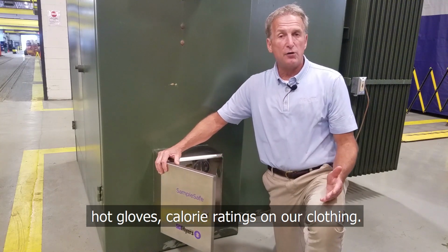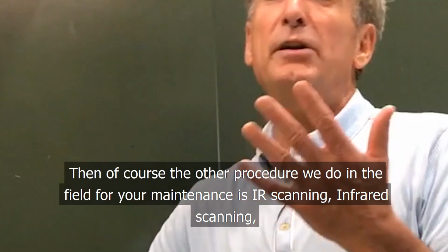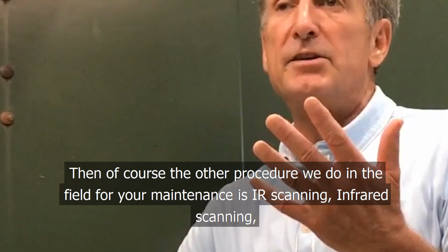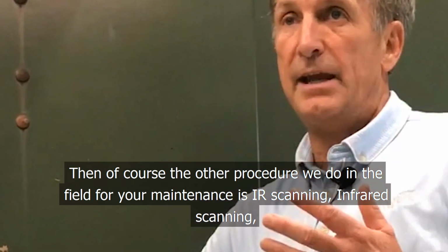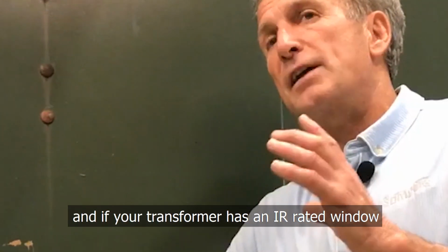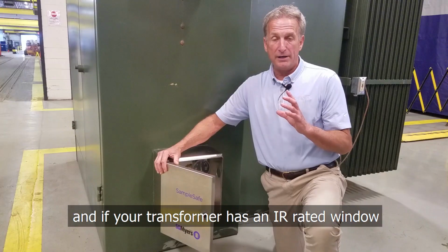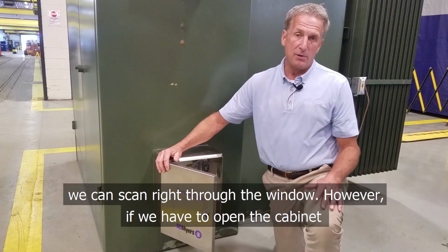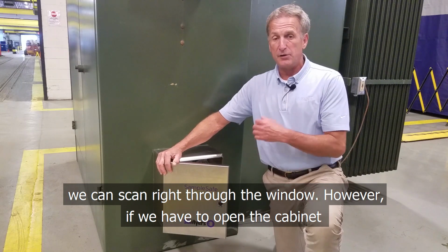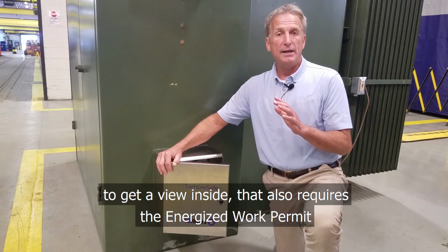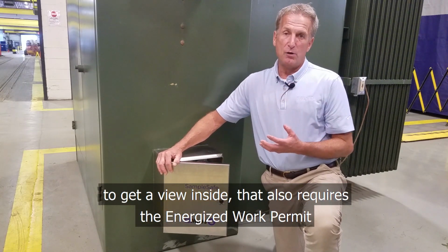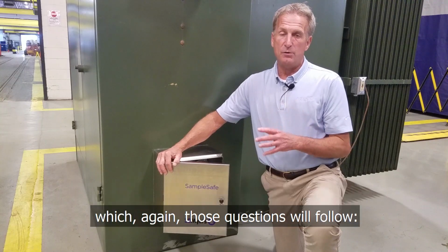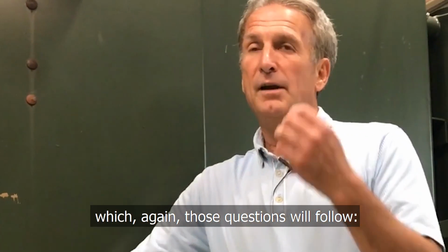And then, of course, the other procedure we do in the field for your maintenance is IR scanning, infrared scanning. And if your transformer has an IR rated window, we can scan right through the window. However, if we have to open the cabinet to get a view inside, that also requires the energized work permit, which again, those questions will follow.